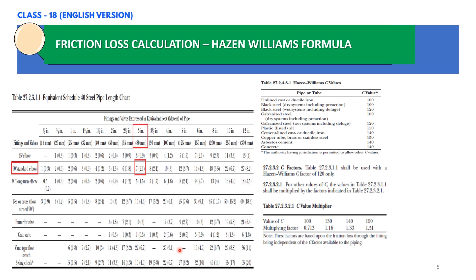This chart is used for schedule 40 steel pipe. If you have other pipe types such as concrete, asbestos cement, plastic, or HDPE pipe, you need to consider the C value and multiply the equivalent pipe length by the appropriate multiplication factor shown in NFPA 13 Table 27.2.3.2.1.